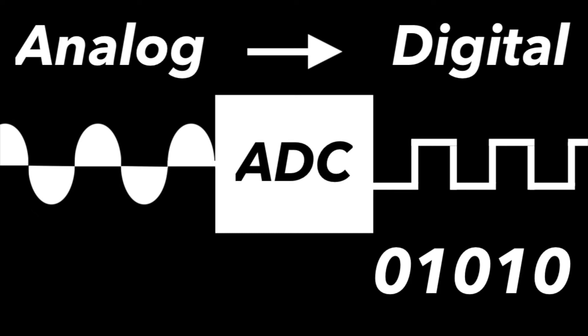This is a language that a computer understands. A digital signal is then processed by the hearing aid's computer chip. A person's hearing thresholds are programmed into the hearing aid's computer chip. This small computer within the hearing aid amplifies, or turns up, incoming sound signals to accommodate for the person's hearing loss.